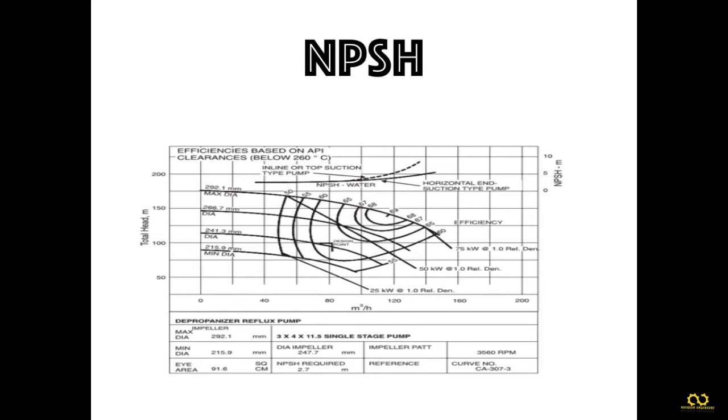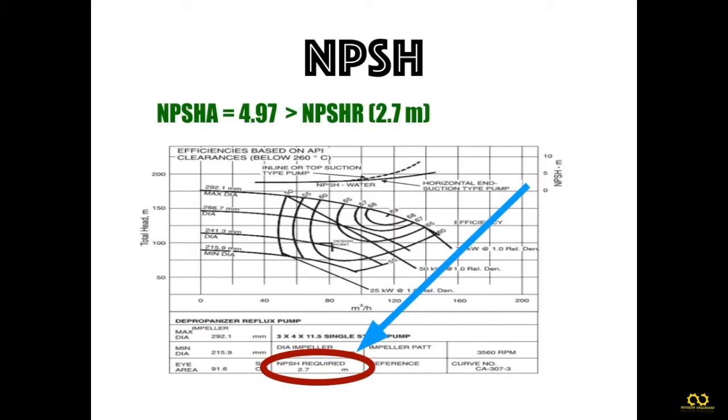Here the given NPSHR, the net positive suction head required, is 2.7 meters. The available net positive suction head is 4.97. Is it okay? Yes, there is no cavitation. Cavitation can be avoided because the value is greater than 2.7 meters, so the pump is running without cavitation.